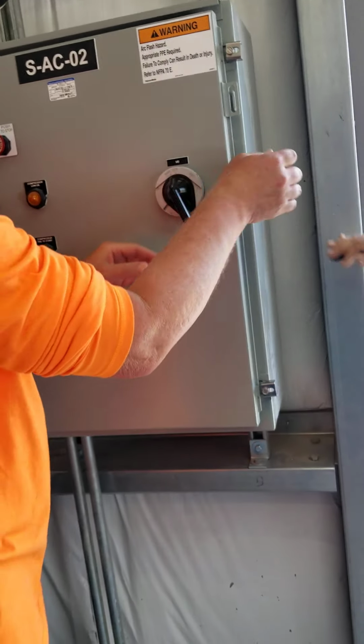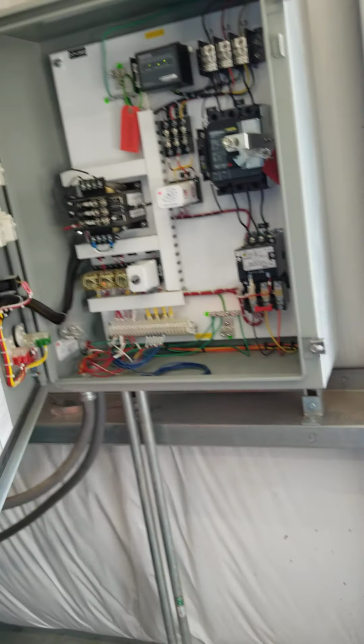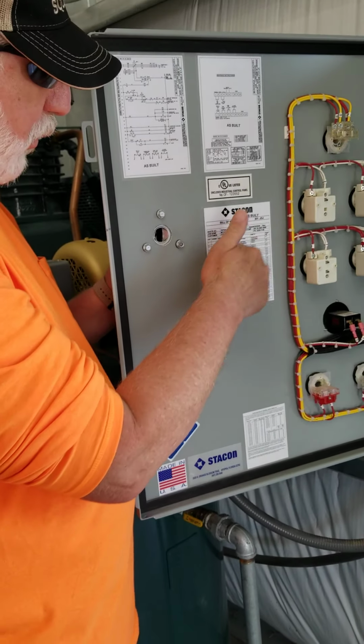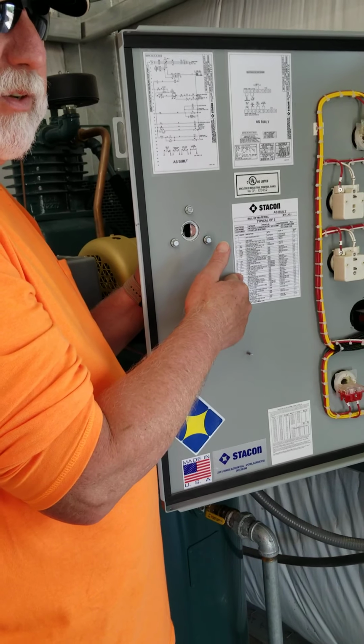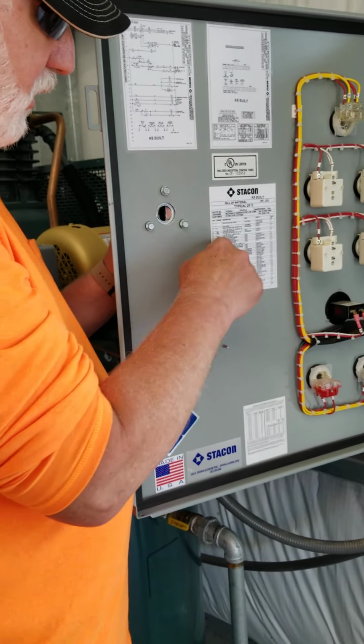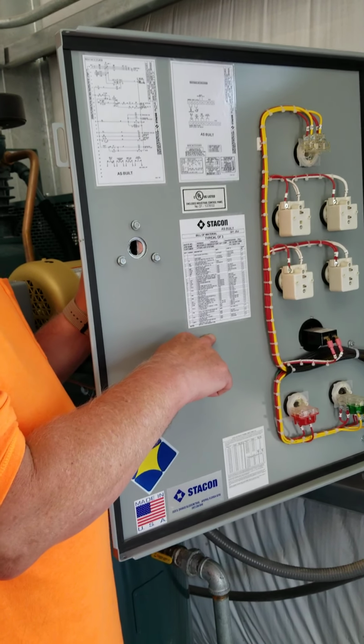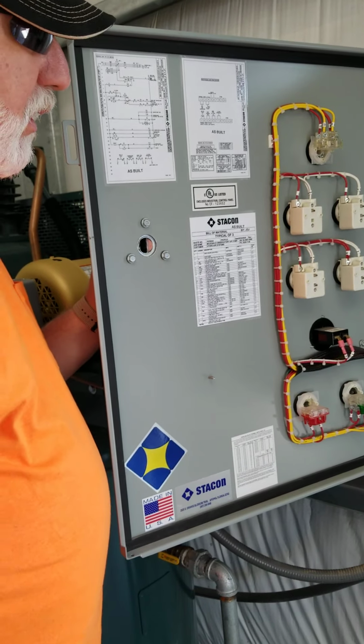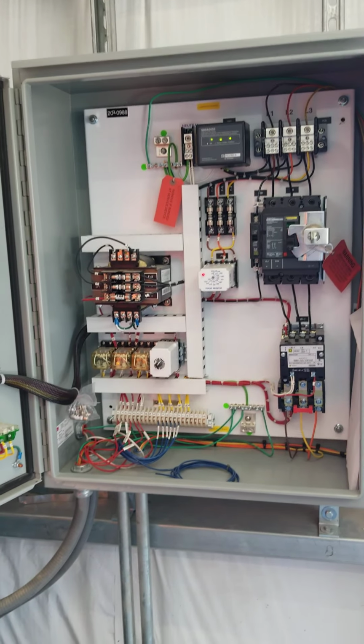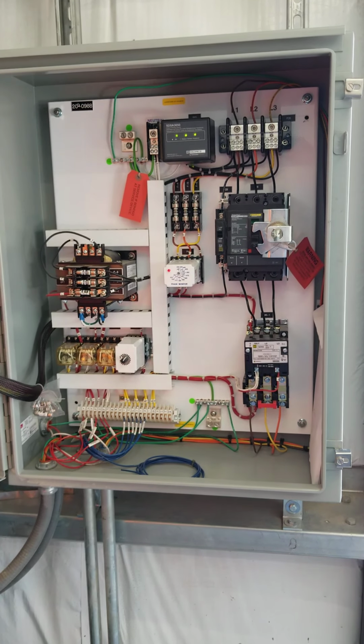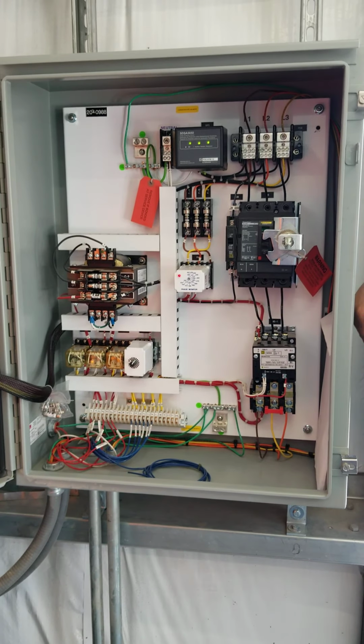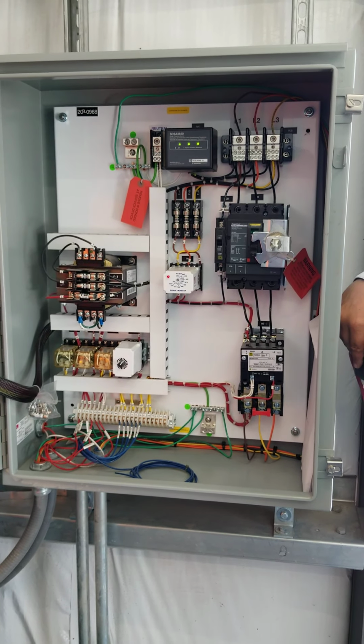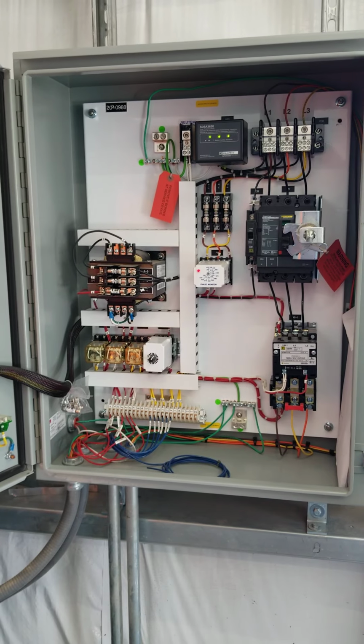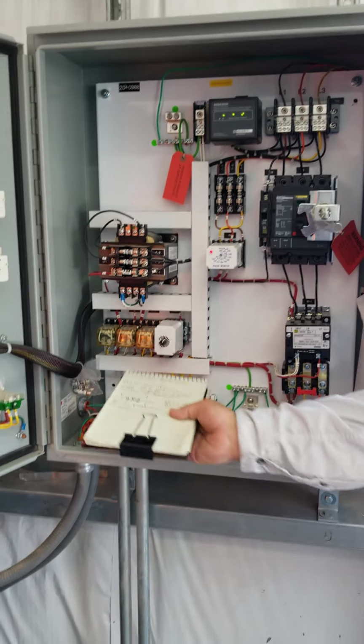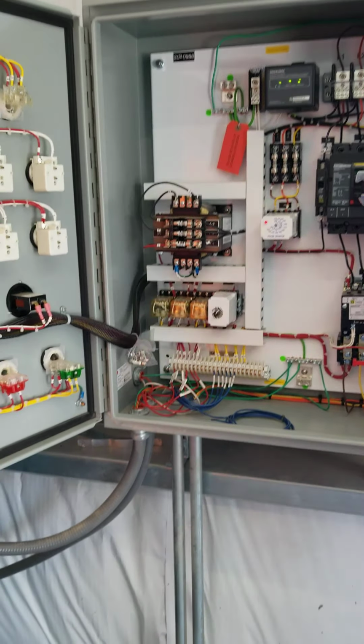One of the main things that I like about these control panels in this company, all your drawings are right here on the door with the bill of materials, so you know everything that's in this unit. So if you have anything failed, you can come right to this list without having to go to a manual or anything else and look it up and see what parts you need. You do in this unit have a surge protector. As long as all 3 green lights are on, you have good surge protection. And you have a phase monitor, so if you lost a phase or something went out of phase, it would shut the control system down so it wouldn't run. Get a few of these to hang on to. Yeah, a few relays are not ever a bad thing to have around.